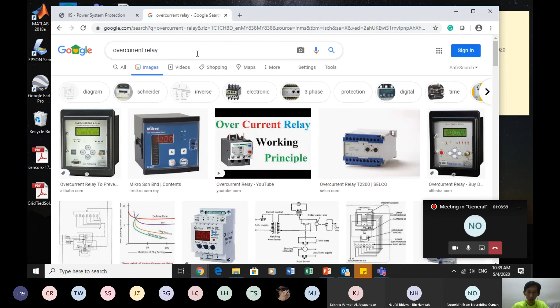Of course, the protection in our houses we call MCB. It looks something like that, right? In your house these are also a circuit breaker. This is a circuit breaker, it's not a protection relay. The difference between a protection relay and a circuit breaker is that a circuit breaker you cannot set. When you buy it, if it is like 20 amps, it's forever 20 amps.